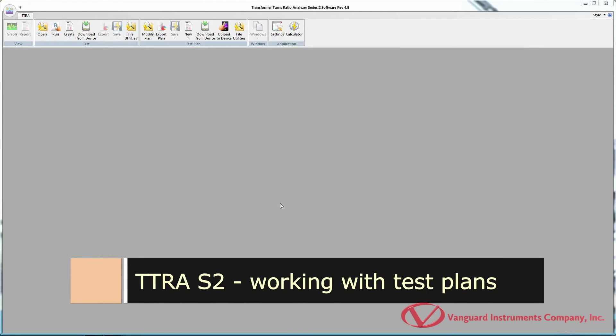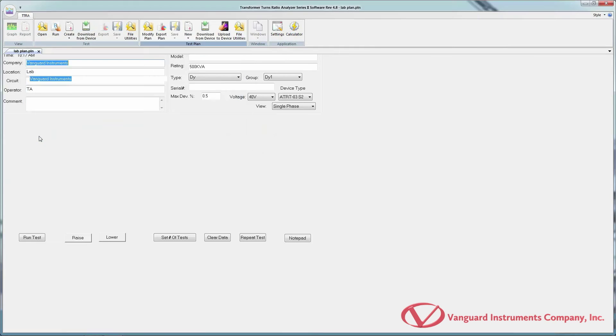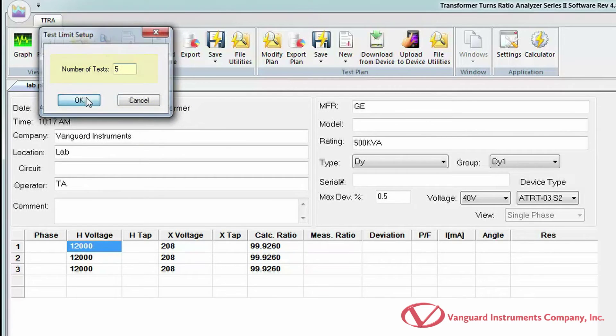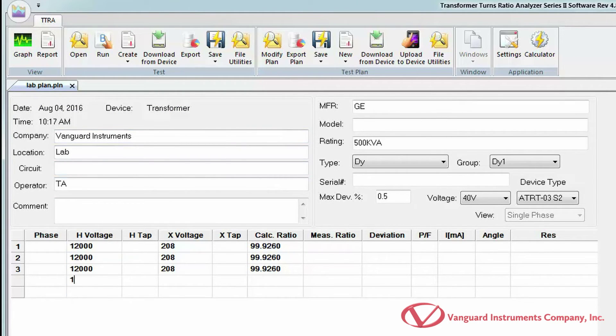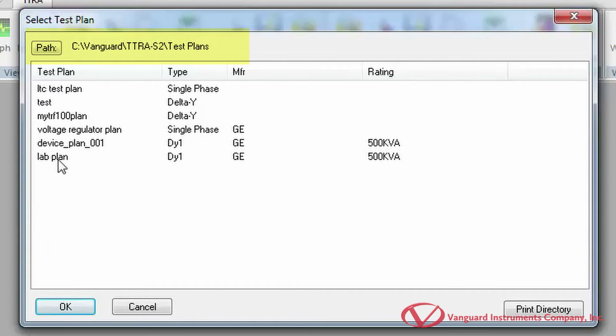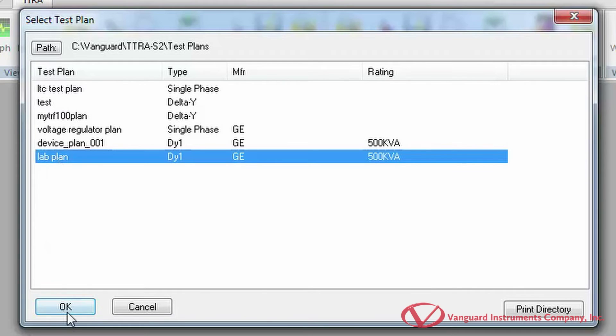The TTRA-S2 software can also be used to create test plans for quickly performing turns ratio tests. Using a test plan, you can define the type of device to be tested, the number of tests to perform, and the parameters for each test. This is a convenient way to perform routine tests on the same transformer, voltage regulator, or load tap changer. Let's modify an existing test plan by clicking on the Modify Plan icon in the Test Plan command group. The top part of this window shows the folder path where test plans are located. Select the test plan you want to modify and click OK.